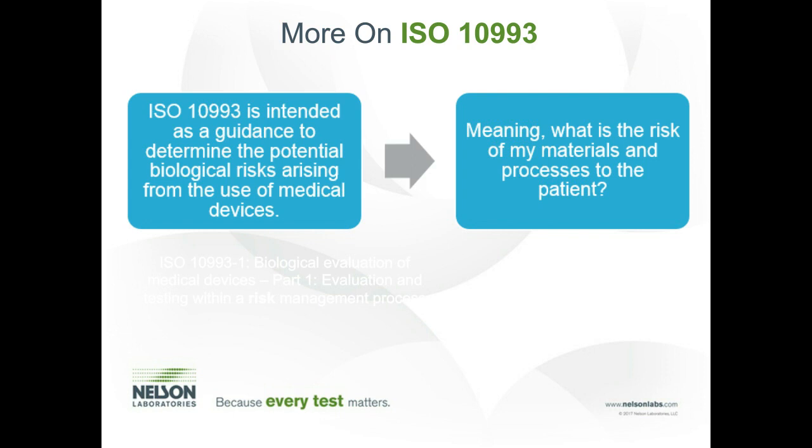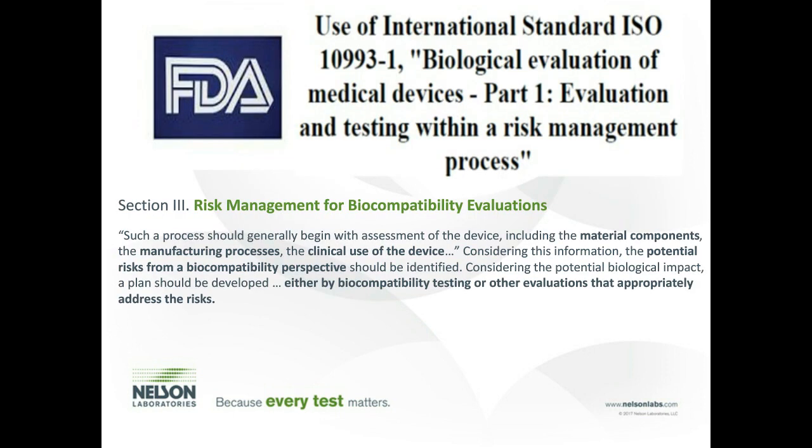I also wanted to hit home, this is part of that new guidance document from the FDA. If you don't think the FDA is going to want to see a risk-based approach, if you think they're relying solely on a checkbox mentality, then you haven't spent the time to read this guidance document. Even in the guidance document itself, as stated here below the title, it is all about a risk-based approach. And in there, they actually want to step away from the checkbox mentality, and they really want you to look at potential risks from the biocompatibility perspective. And if it's limited, and you can evaluate the risk through material and process justifications, then there are ways we can do limited biocompatibility testing because those risks have been mitigated in other ways.